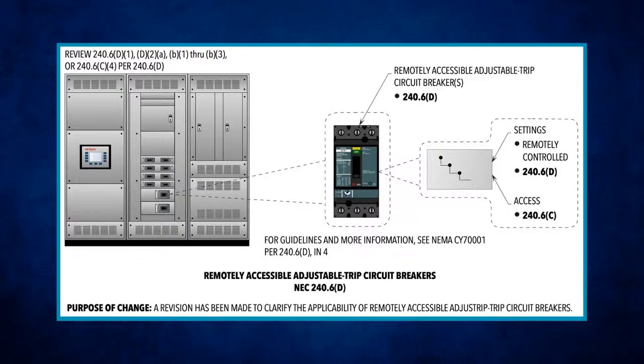And when you get to your switchboards, what does it deal with? It's to distribute power to your lower voltages. I guess that's the best way I could explain that. And I would say an MCC is kind of like a little bit more of a unicorn compared to those, because you don't really know what voltages you're controlling in that MCC. You could have some motors that are 480, some that are 4160 coming off that same MCC, so it kind of isolates your different motors through that motor control center.